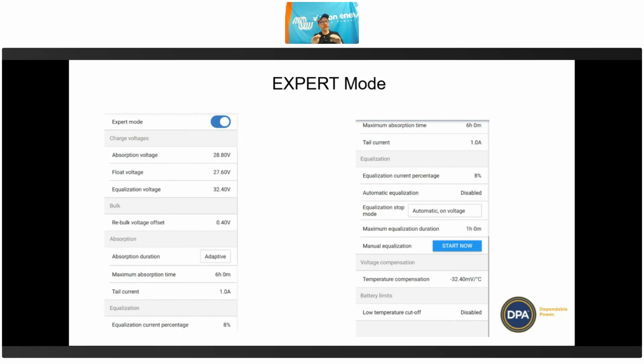But then at some point you need to determine, well, the voltage is going to fall below that. At some point, I want to start the algorithm again. I don't want it to keep going round and round. But once the battery voltage gets to a certain lower set point, then we restart this algorithm and bring it all the way back up to the top.